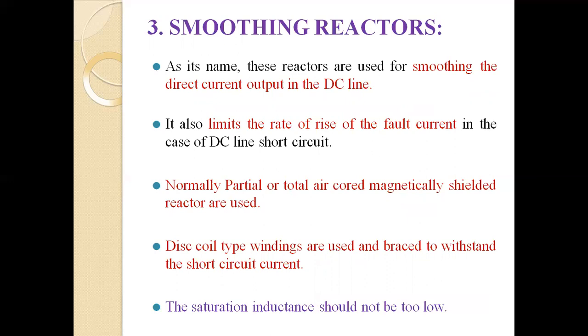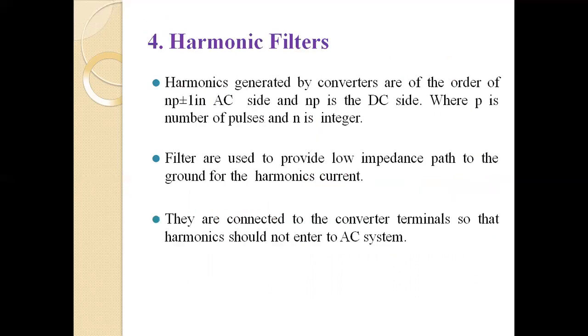Normally, air core magnetically shielded reactors are used. Disc coil type winding is used and braced to withstand the short circuit current. The saturation inductance should not be too low. Next part is the harmonic filter.